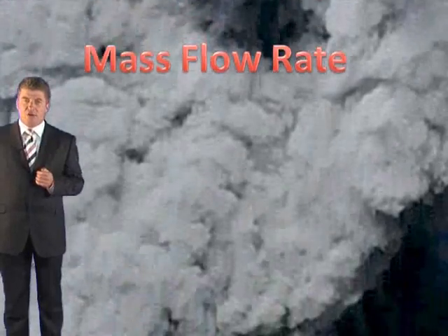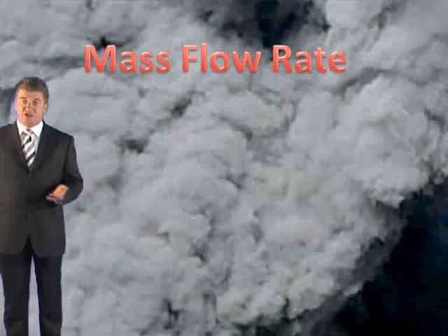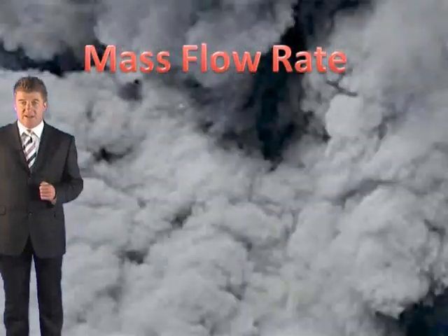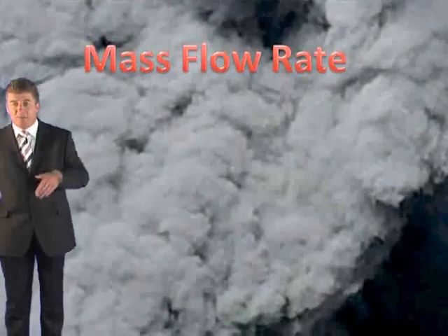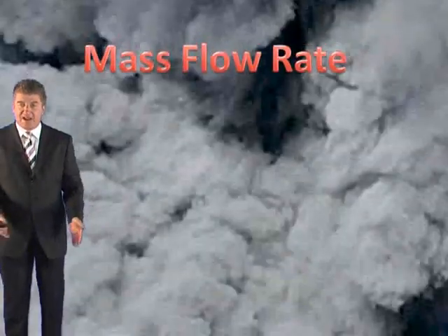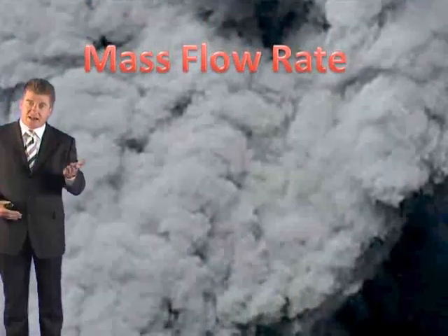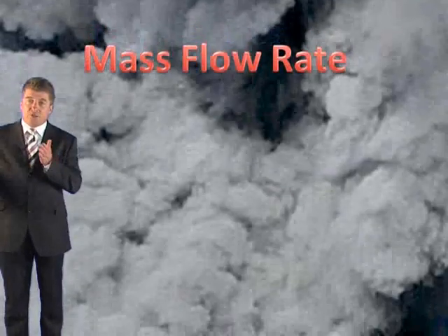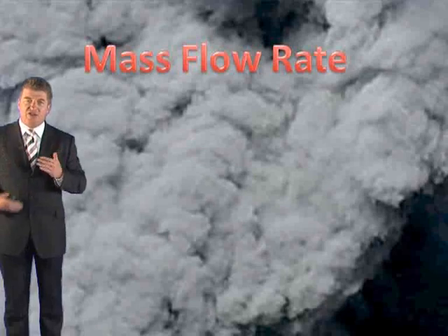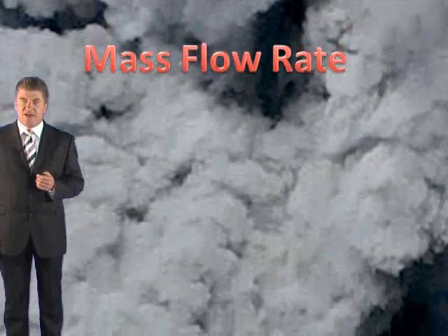M is your mass flow rate of smoke. In this step, you've got to determine the mass flow rate of smoke which is emanating from that design fire size. You might have a simple plume, you might have a complex plume. Simple plume, where the fire originates in the room where it's been extracted. A complex plume, like a shopping mall, is where it's got to travel down corridors before it reaches a spill edge. So that's your mass flow rate of smoke.